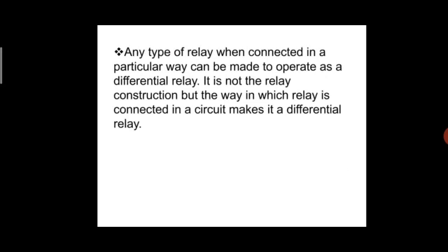Any type of relay, when connected in a particular way, can be made to operate as a differential relay. It is not the relay construction, but the way in which the relay is connected in a circuit that makes it a differential relay.